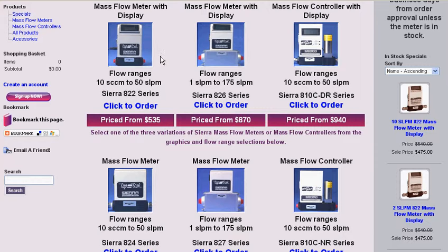So Sierra is a strange company and unique in that we calibrate with primary standards. That's because, as the developer of Sierra, I'm the engineer with the patents on this. I designed a primary standard that Sierra used to sell called the CalBench, and that's used in most of the standards labs, and Swiss standards labs, NIST, and most of the large companies have that as a primary standard.